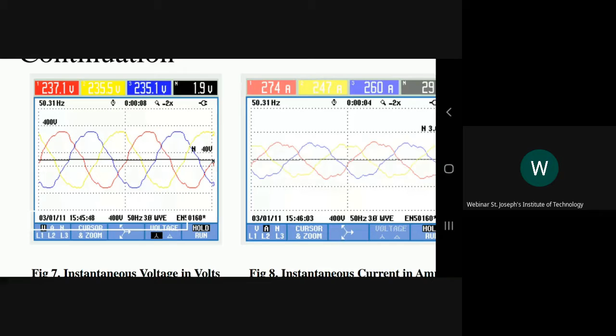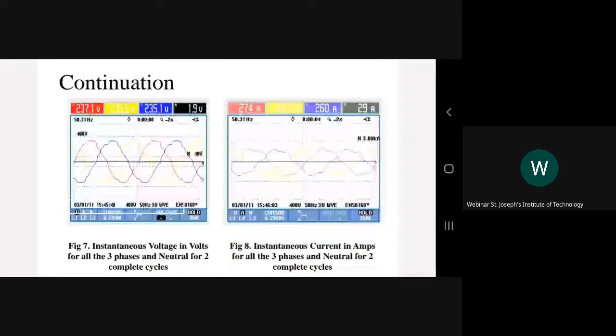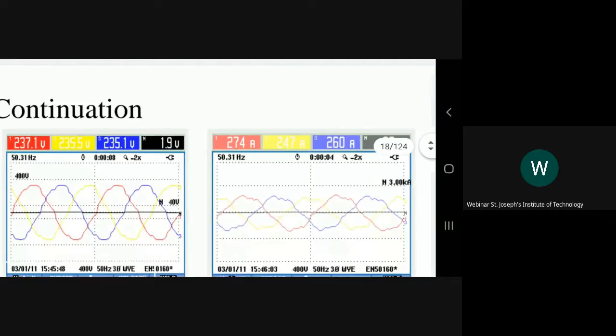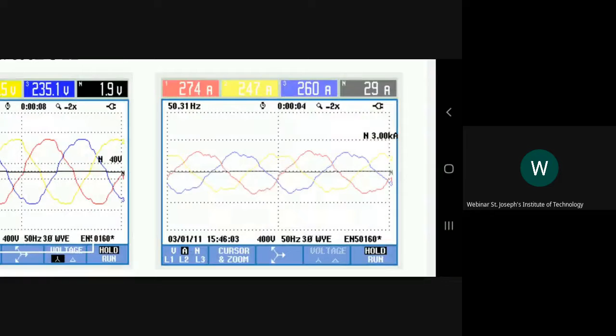Figure 8 shows the instantaneous current in amperes for all three phases and neutral, again for two complete cycles. For these two cycles, the current for the red phase is around 274 ampere, the yellow phase 247, and the blue phase 260 ampere.